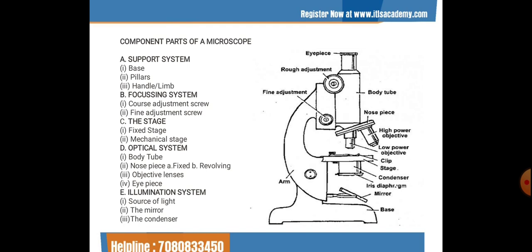The objective must be constructed so that it can be focused close enough to the specimen so that it will project a magnified real image up into the microscope. The high power objective should have a retractable front lens housing to protect the front lens where the objective requires focusing very close to the specimen. To the extent possible, correction for lens error should be made with the objective itself.